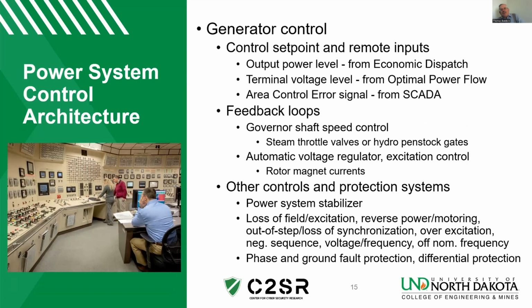Now, the generator set points are what we would wish to have the generators operate at, and that's coming from our economic dispatch and optimal power flows for our voltage and power output, as well as our area control errors, which are generated by the SCADA system. So these form the inputs into our control loop. For the feedback loops, we measure the speed off the shaft and take that back to the governor, which will then adjust either the steam valves or the penstock gates for hydro. The excitation then controls the voltage output of our generators, and we measure the voltage to make sure it's within the values that we want the generator to operate at. So we have two feedback loops inside the plant.